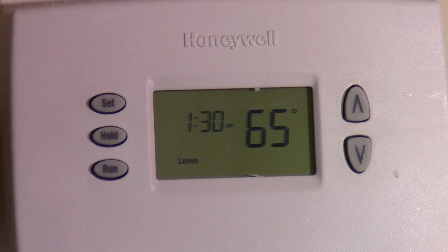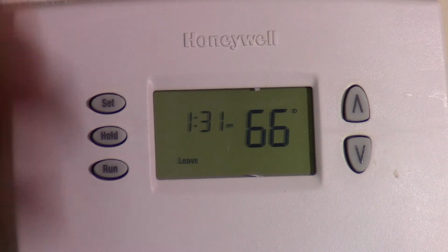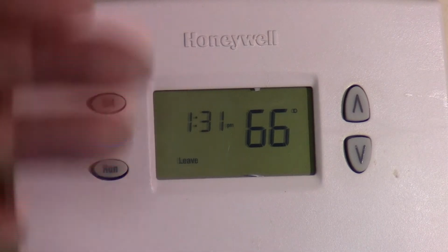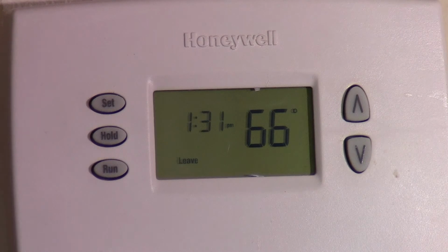So you either have the boiler or thermostat on 3 times an hour, 4 times an hour, 5 times, 6 times, or 2 times. So my thermostat was set at 5 times, which is not the suggested number of cycles per hour. For my heating system, which is a hot water system, the recommended is 3 cycles per hour.